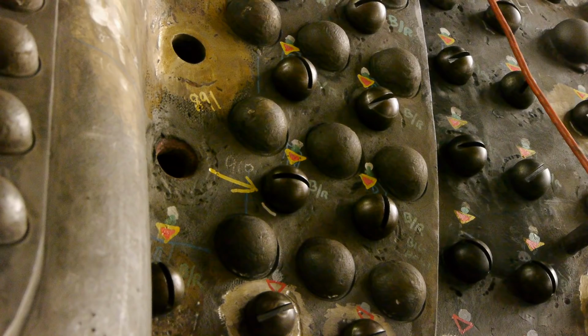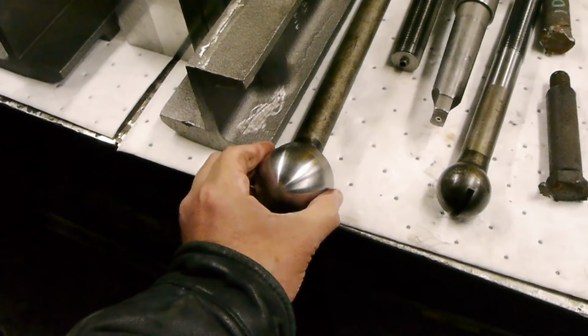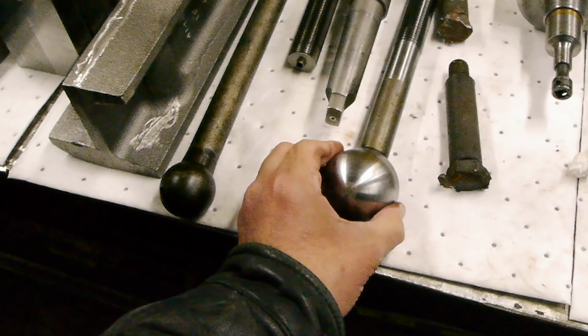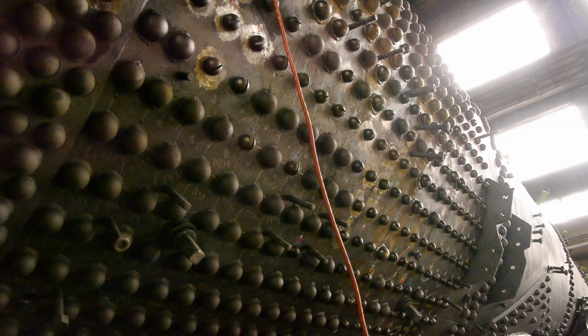The flexible stay bolts then have a cap welded over the end of it to keep the steam pressure inside. All of this is built right here in the shops on the CNC lathe in the other room. Here you can see how the cap fits over the flexible stay bolt. Multiply this operation something like 2,000 times and you now have a rebuilt boiler.